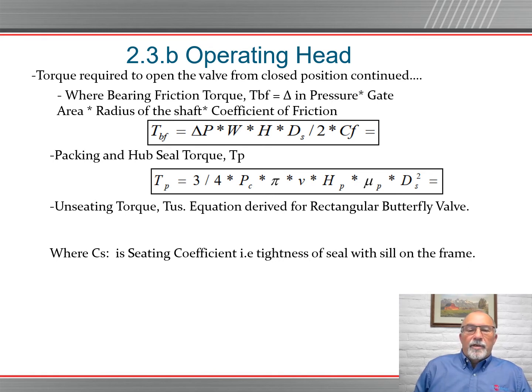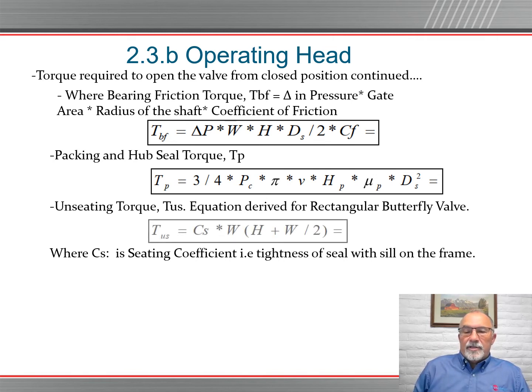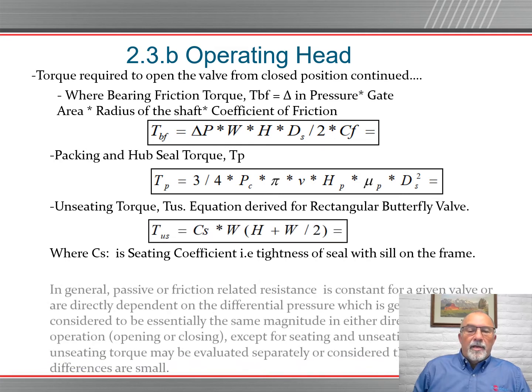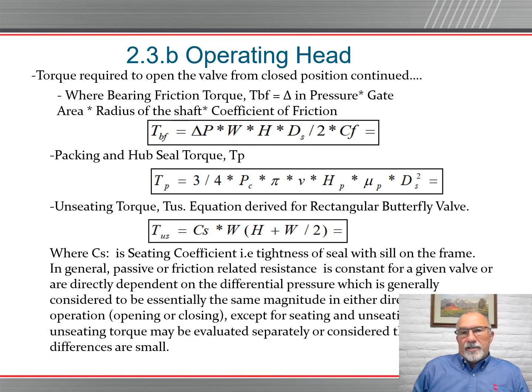The unseating torque, the equation derived from the rectangular butterfly valve, talks about the seating coefficient, the tightness of the seal on the seat on the seal frame. And there's the calculation. In general, passive or friction related resistance is constant for a given valve or is directly dependent on the differential pressure, which is generally considered to be essentially the same magnitude in either direction of operation, opening or closing, except for seating and unseating. Seating and unseating torque may be evaluated separately or considered the same when differences are small.